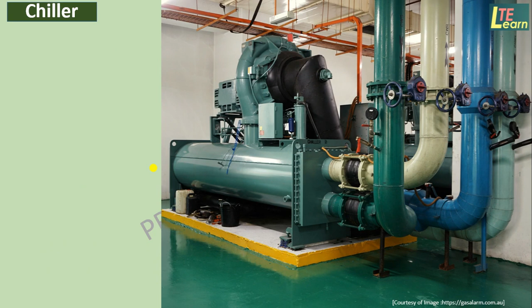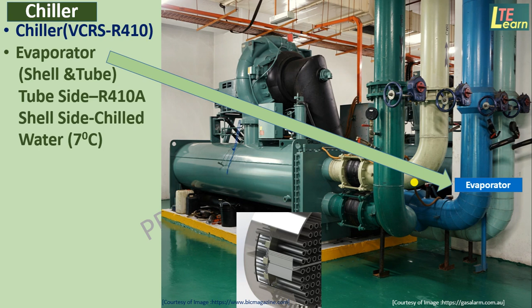The chiller has a vapor compression refrigeration system which uses refrigerant R410A as the primary refrigerant. The evaporator is of shell and tube type, where the tube side carries the primary refrigerant R410A, and the shell side carries chilled water inside the shell. The condenser is here of shell and tube type. In this, it carries refrigerant R410A on the shell side and water on the tube side.